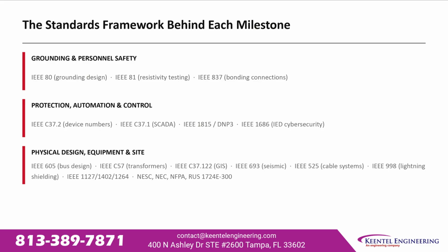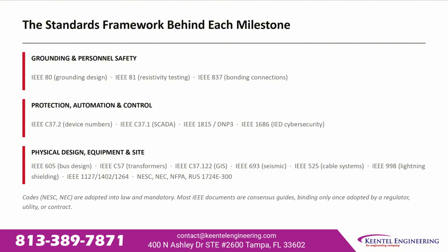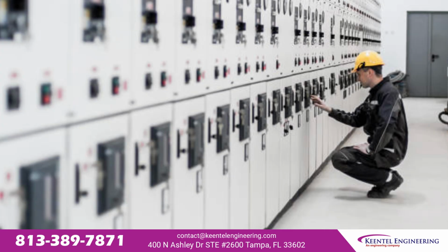For physical design and equipment, IEEE 605 for bus design, IEEE C57 for transformers, IEEE C37.122 for gas-insulated switchgear, IEEE 693 for seismic qualification, IEEE 525 for cable systems, and IEEE 998 for lightning shielding. NESC and NEC are codes adopted into law and are mandatory on every project. Most IEEE documents are consensus guides, binding only when adopted by a regulator, utility, or contract.